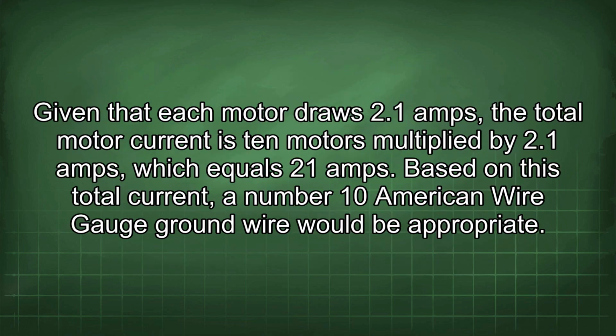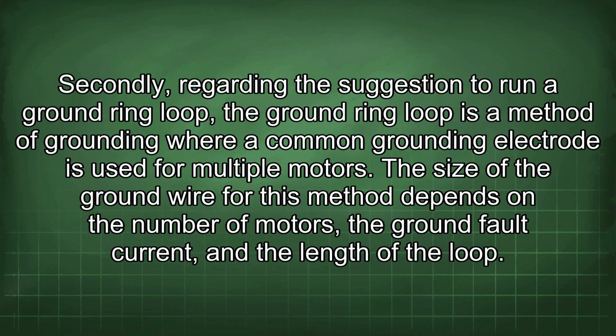Given that each motor draws 2.1 amps, the total motor current is 10 motors multiplied by 2.1 amps, which equals 21 amps. Based on this total current, a number 10 American wire gauge ground wire would be appropriate. Secondly, regarding the suggestion to run a ground ring loop, the ground ring loop is a method of grounding where a common grounding electrode is used for multiple motors.